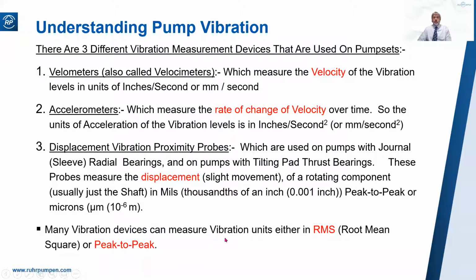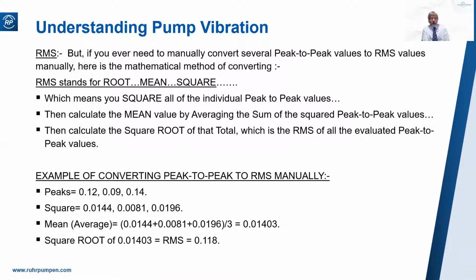Many vibration units will measure vibration either in RMS or in peak-to-peak. Most commonly, they're given in RMS values, with peak-to-peak values used for detailed analysis. So RMS, root mean square, which means you take all your peak-to-peak values, you square them, you take the average, and then square root that total. So for example, if you've got 3 peaks here, you square them, add them together, divide by the total number, and then square root it. So the RMS of these 3 peaks is 0.118.